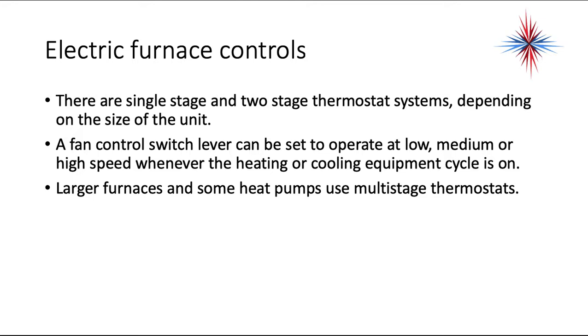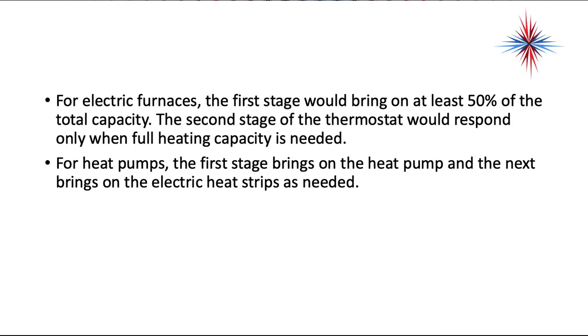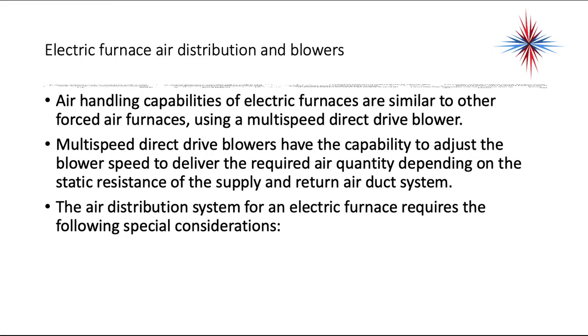Larger furnaces and some heat pumps use multi-stage thermostats. For electric furnaces, the first stage would bring on at least 50% of the total capacity. The second stage of the thermostat would respond only when the full heating capacity is needed. This is energy savings. This would be like for what we consider the shoulder seasons, the spring and the fall, where you don't need all of the electric heat and you can only use part of it. For heat pumps, the first stage brings on the heat pump and the next stage brings on the electric heat strips as needed.